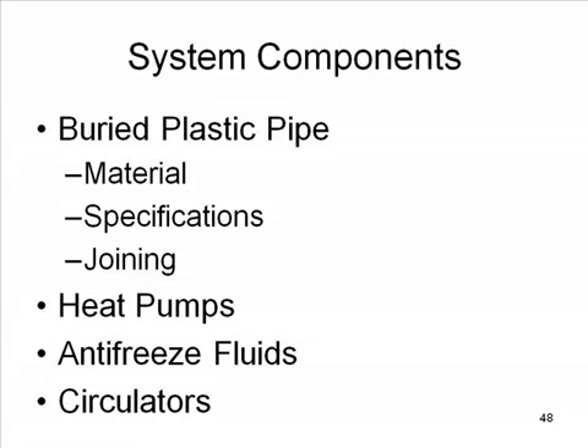Heat pumps, there are 3 different kinds of levels of heat pumps depending upon application. You have cooling tower and boiler, you've got groundwater, and then you've got geothermal, and each one of these has a temperature range which require different kinds of heat pumps. But what really dictates which one of those heat pumps you use are the range of fluid temperatures that are going to come to it. You wouldn't want to use a geothermal heat pump project in a commercial building where the cooling tower and boiler was going to obviously control the temperature much more closely than the temperature ranges that you get with geothermal.